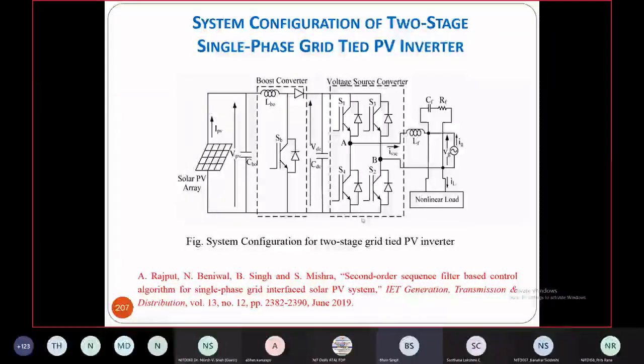So the panel open circuit voltage will be around 440 or 450. So if you have an open circuit voltage of 440, all the devices have to be rated 450 volt, not 400 volt. But in this case, you can take an open circuit voltage of the PV equal to the DC link voltage, that is 400. It means all the devices can be of 400 volt, not necessarily 450 volt, so you don't need to derate the devices. That is one benefit.